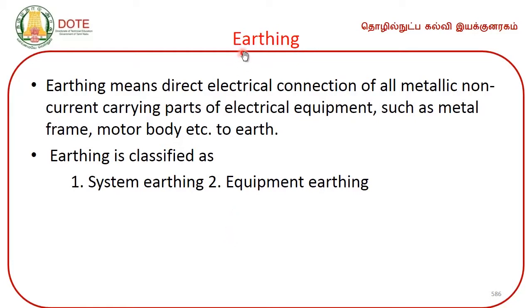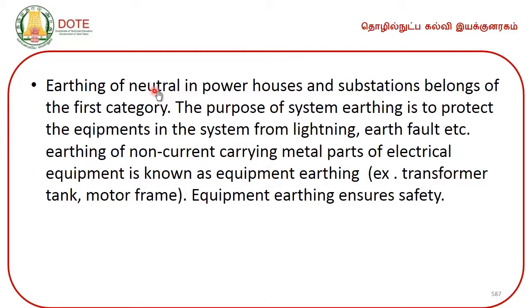Then we will come to the important topic called earthing. Earthing means direct electrical connection of all metallic non-current carrying parts of electrical equipment such as metal frame, motor body, etc. to earth. Earthing can be classified as number 1, system earthing, number 2, equipment earthing. Earthing of neutral in powerhouses and substations belongs to the first category. The purpose of system earthing is to protect the equipments in the system from lightning, earth fault, etc. Earthing of non-current carrying metal parts of electrical equipment is known as equipment earthing.